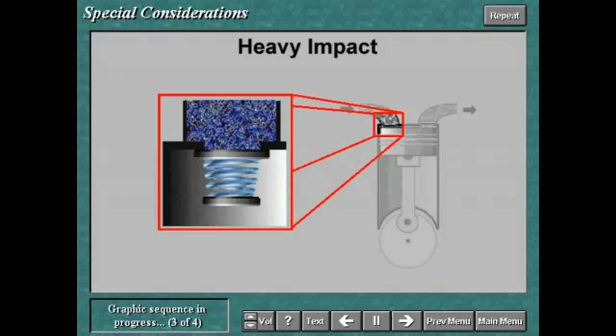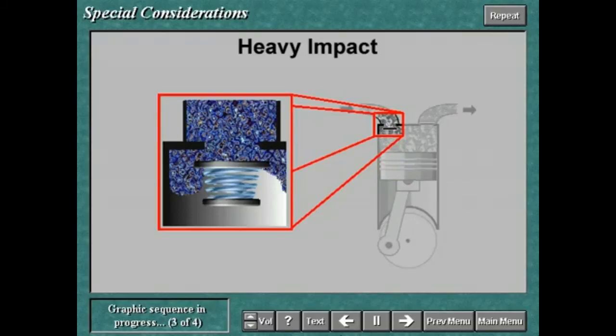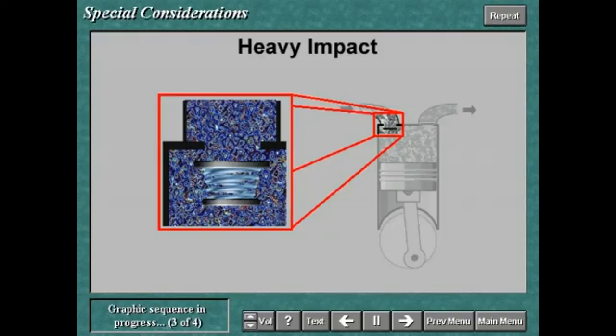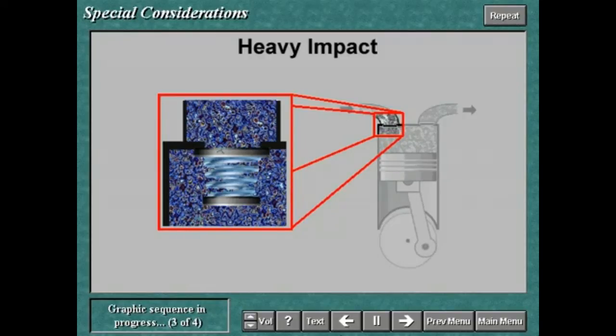If the valve remains open after the dead end of the stroke, closure will happen under both spring force and gas force due to backflow of the gas. The combined effect will result in a heavy impact and likely ring damage.